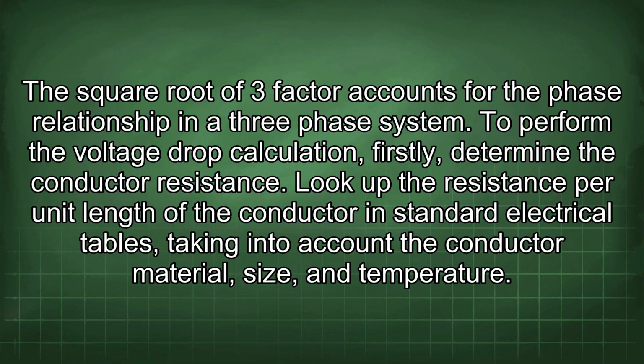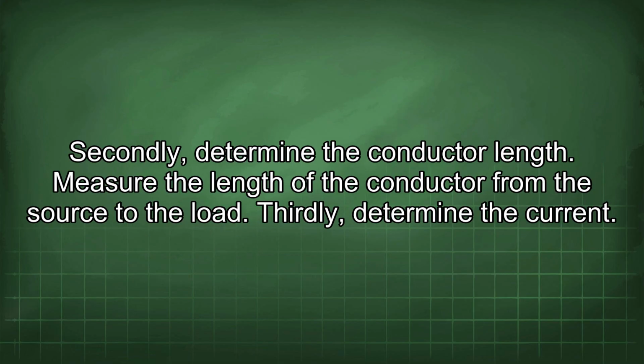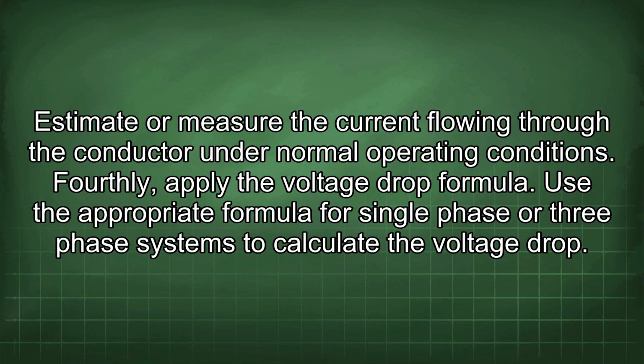To perform the voltage drop calculation, firstly determine the conductor resistance. Look up the resistance per unit length of the conductor in standard electrical tables, taking into account the conductor material, size, and temperature. Secondly, determine the conductor length. Measure the length of the conductor from the source to the load. Thirdly, determine the current. Estimate or measure the current flowing through the conductor under normal operating conditions.